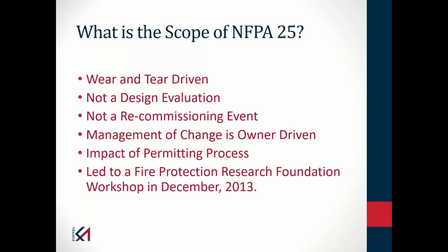Now, some people will argue that NFPA 25 is a wear and tear document. In other words, it doesn't really do much for me except tell me whether there's been some deterioration of my system, that my sprinklers are corroded or loaded or have paint on them or whatever the case might be. I don't buy into that concept. I will share with you, and you'll hear me talk about this again a little bit later, that the inspectors or the individuals that are required to do the inspection activity do not need to evaluate the design and installation requirements. So in that sense, yes, the inspection activity is more of a wear and tear activity, but the owner still has the responsibility to make sure that the system is adequate for the hazard being protected.